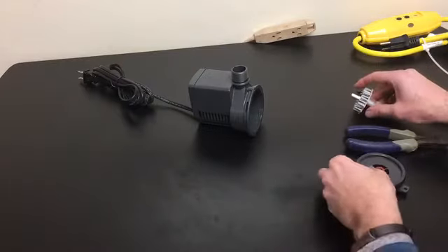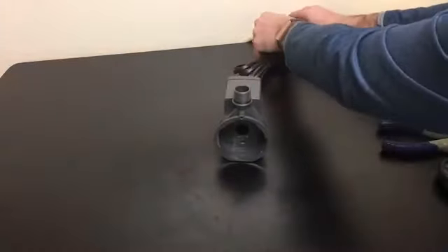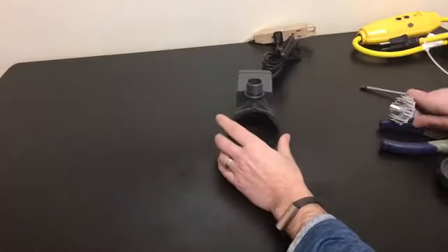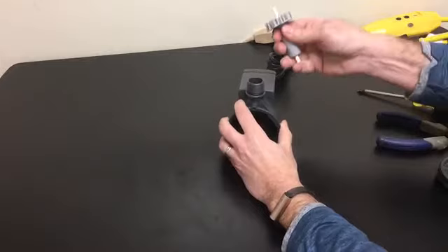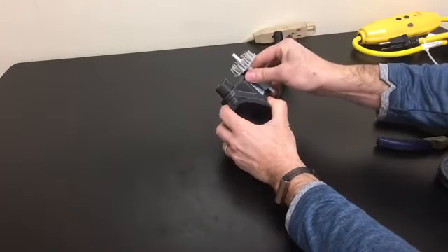Now if you're going to do a motor block check on any pump, you can do it out of the water. So what you would do is plug the pump in. So I've got the pump plugged in. I've already done the other inspections. Hold the rotor firmly, and get to the side. You can feel the vibration.